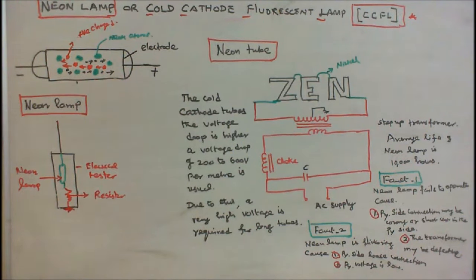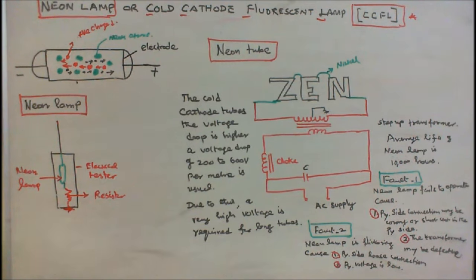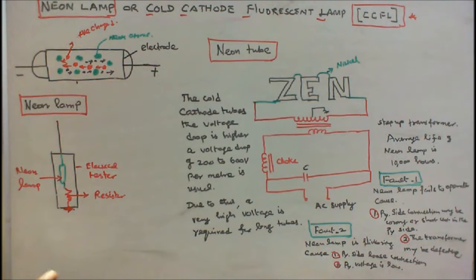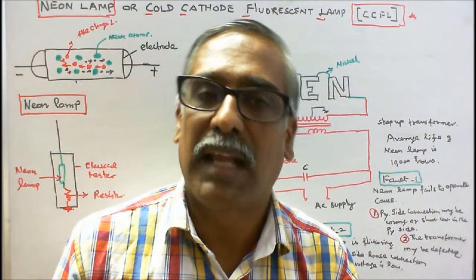Now we will see the types of faults. Fault 1: Neon lamp fails to operate. Causes: number one, primary side connection may be wrong or there may be a short circuit in the primary side; number two, the transformer may be defective. Fault 2: Neon lamp is flickering. Causes: number one, primary side loose connection; number two, primary voltage is very low. This is a common fault that occurs in the neon lamp. With this I conclude my lecture. Thanks for listening.